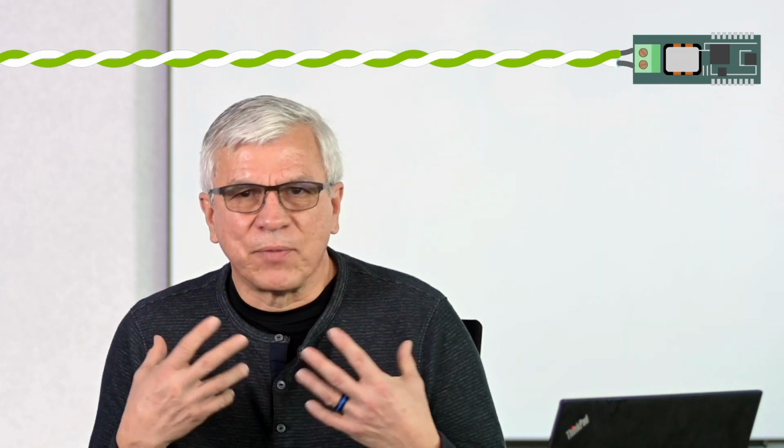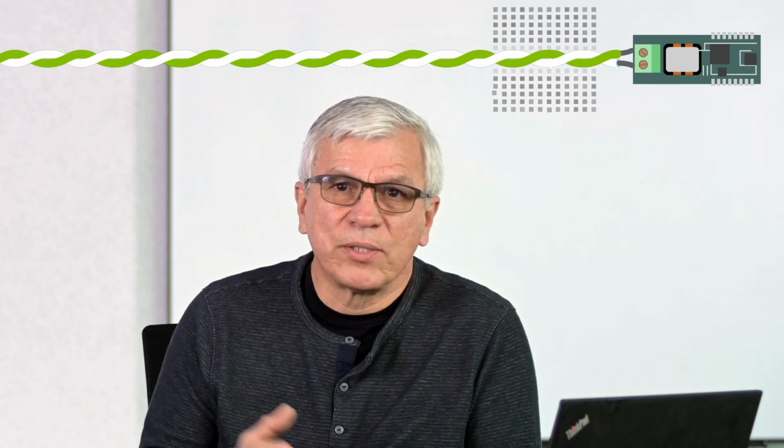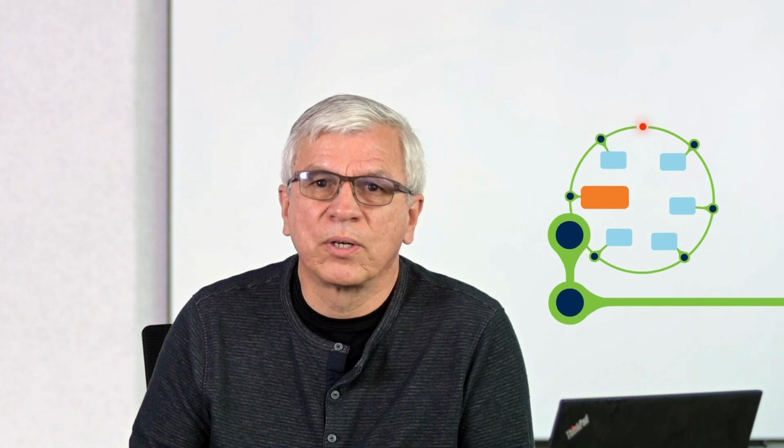FT is a wired communication technology that uses only two wires. That makes it very simple to install. You can install the wires in either way, so it's polarity insensitive. So there's no way to hook up the endpoint incorrectly. It is highly noise immune, so if there are noise sources in the back, it continues to work. It's fault tolerant, so if there's a break somewhere in the wires, things can continue to work.